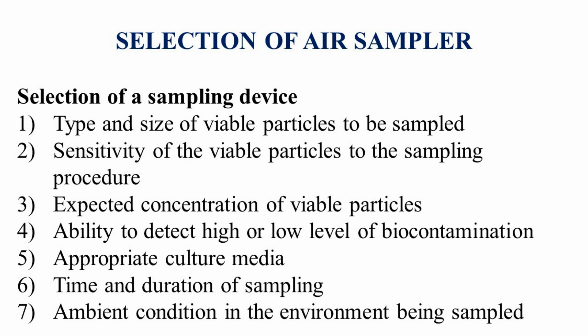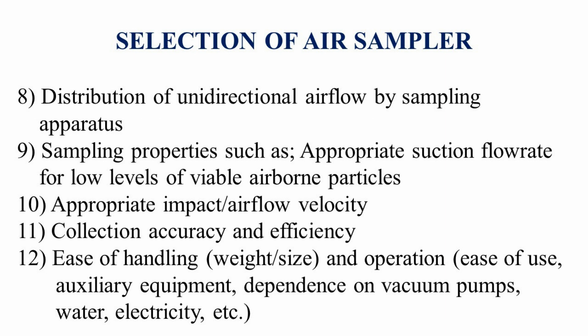Seventh is the ambient condition in the environment being sampled. The air sampler should work at ambient temperature and also in low and high temperatures. Eighth is the distribution of unidirectional air flow by the sampling apparatus. The selected air sampler should be capable of distributing air uniformly and unidirectionally; uneven distribution leads to false negative results. Ninth is sampling properties such as appropriate suction flow rate, and the sampler should have different flow rates and sampling times to help adjust volume as per biocontamination occurrence chances.